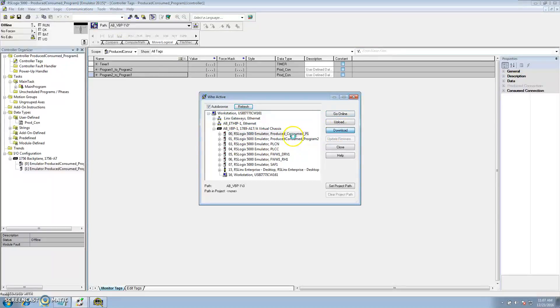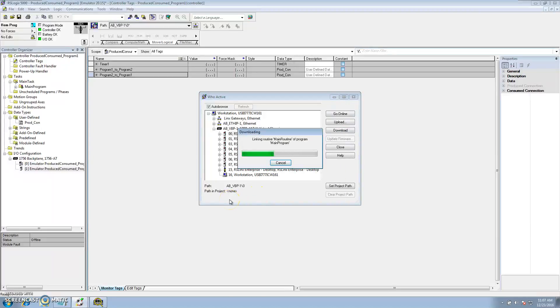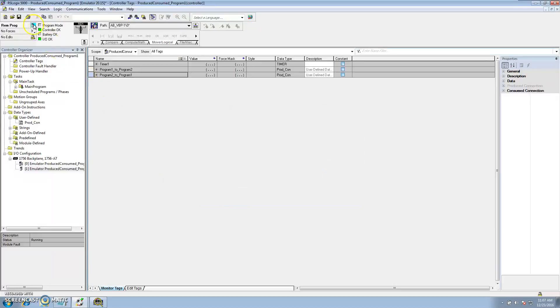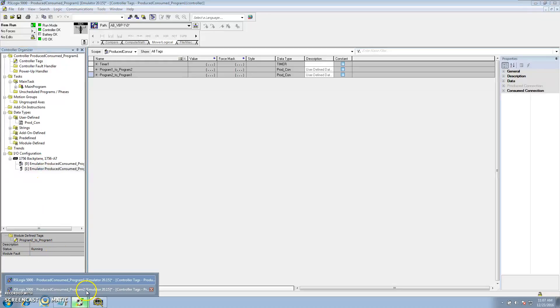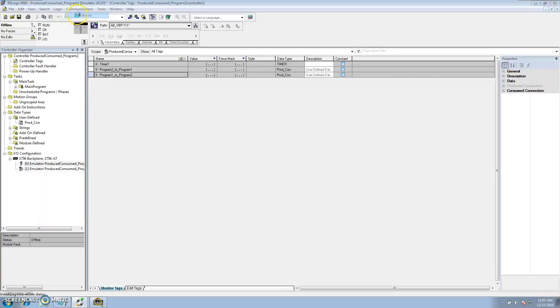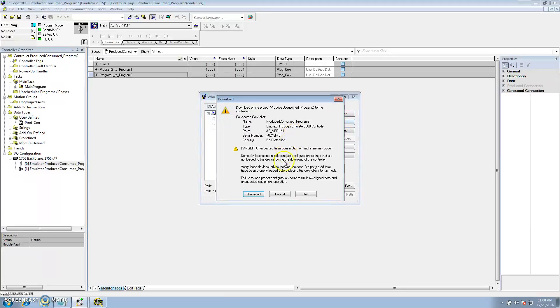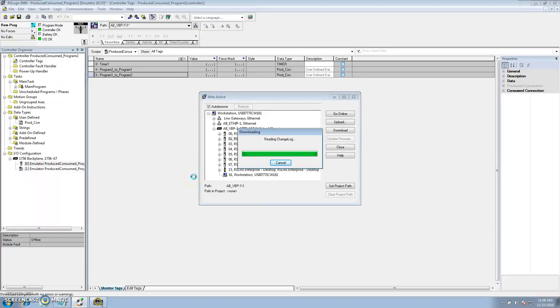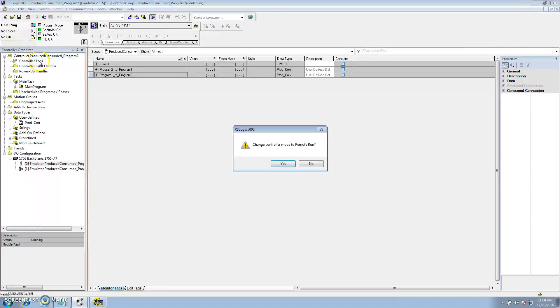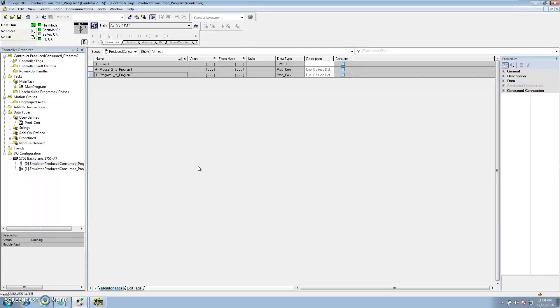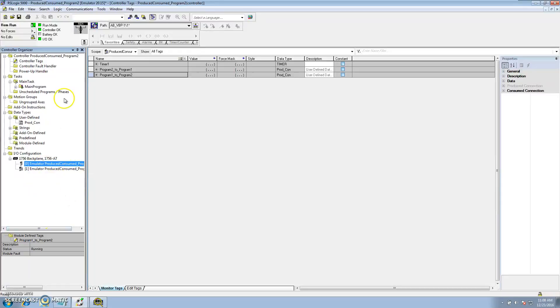Now we'll download. Program One is in slot zero, so I download it to slot zero. As long as everything is done correctly, you will not see any triangles or caution symbols — they should show that they're running and everything is fine. Let's go to Program Two and do the same thing. Program Two is in slot one, so we download to slot one. You would have seen caution symbols or a triangle indicating a connection failed if something was wrong, but now everything is working.